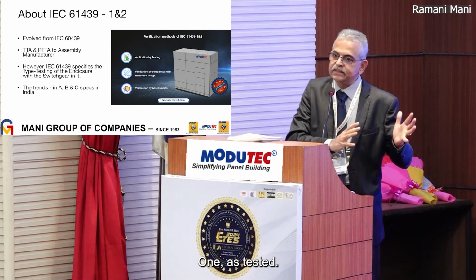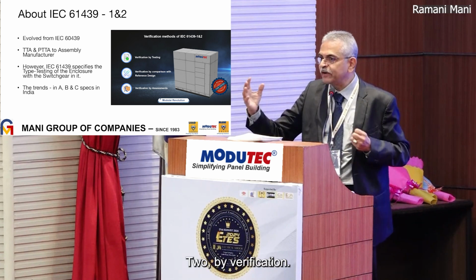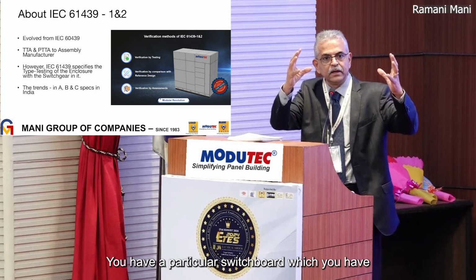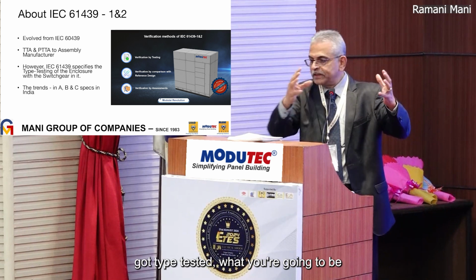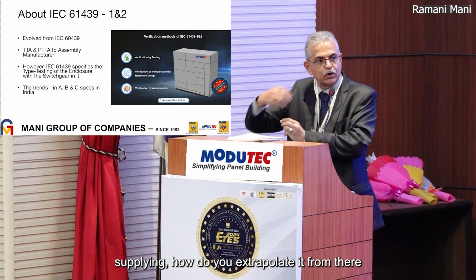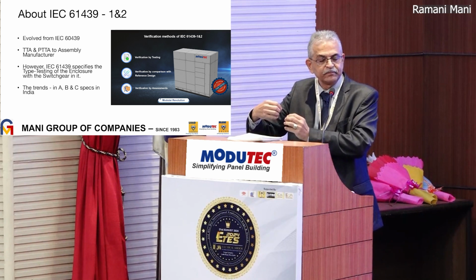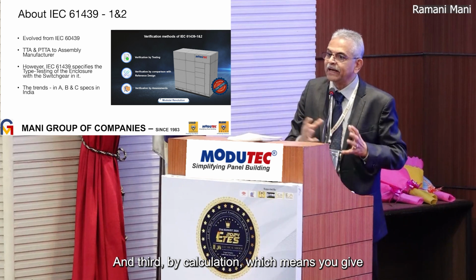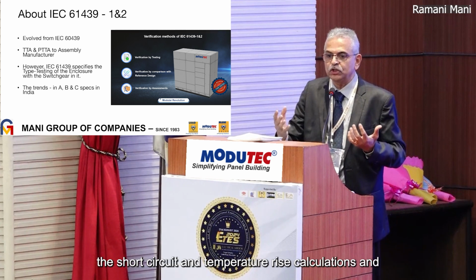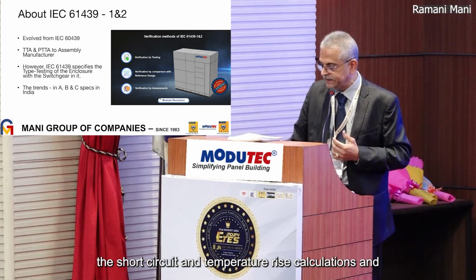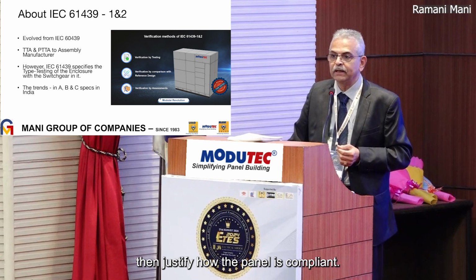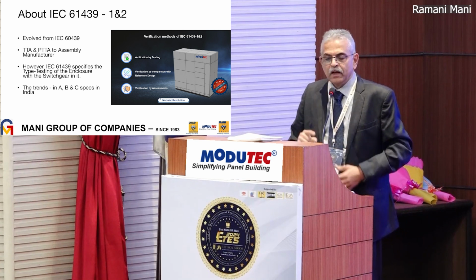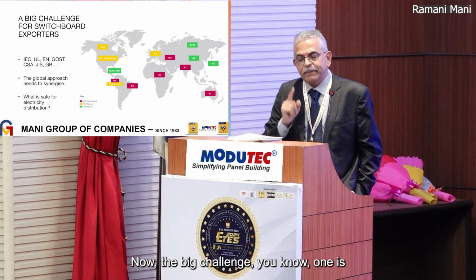One, as tested. Two, by verification - you have a particular switchboard which you have got type tested, what you're going to be supplying, how do you extrapolate it from there to here. And third, by calculation, which means you give the short circuit and temperature rise calculations and then justify how the panel is compliant.